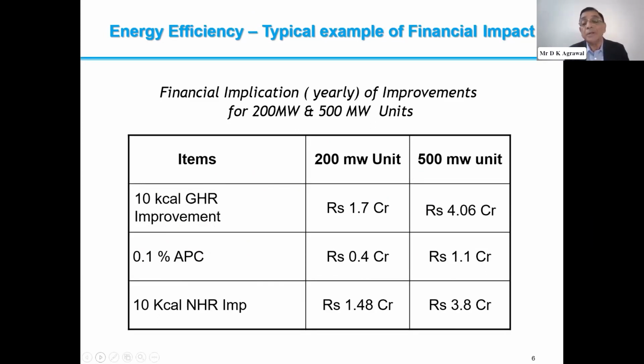As such, I have another view on this. We talk about supercritical, ultra supercritical, and all that effort is to further improve the heat rate. Now, at the same time, we need to understand that after a certain stage, even 1 kilocalorie improvement, when we talk about supercritical and ultra supercritical, the design cost implications are going to be of the order of 4 to 5 crore. That's something you lose just like that.